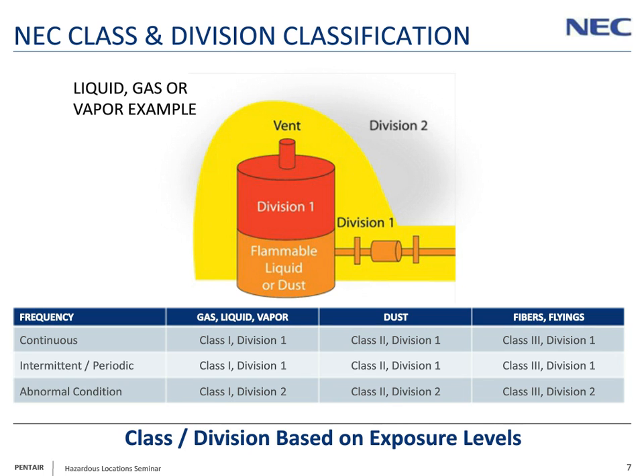So once you define the class, there are different divisions. In this example, we see here a tank, and a Division 1 is an area where you have continuous or intermittent or periodic exposure. So if you're installing equipment on the tank that's full with gasoline, for example, or equipment really close to that tank, you're typically in a Division 1 area. Division 2 is when that hazardous material is present only during an abnormal condition. So they break things up into those Division 1, Division 2 areas. They're very technical definitions of what a Class 1 or what a Division 1 is versus Division 2, but in layman's terms, this is how they are applied.